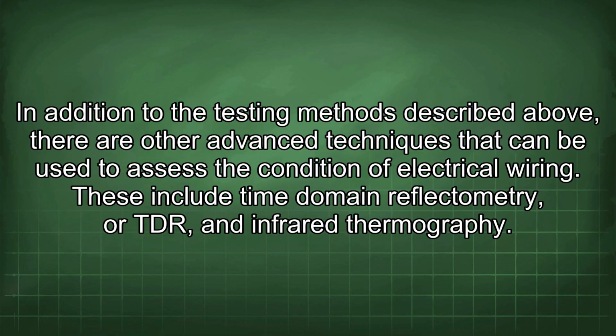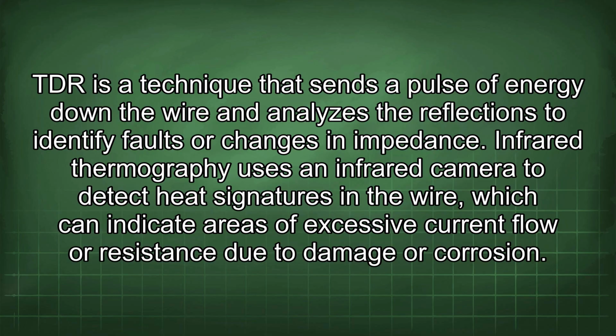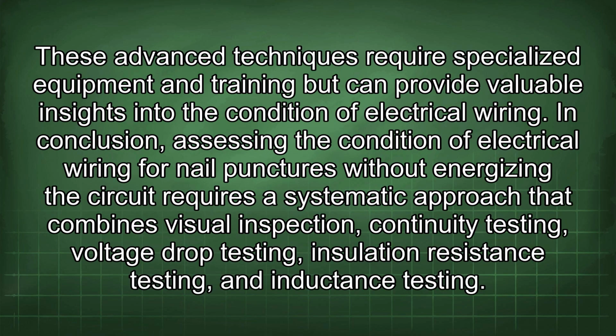In addition to the testing methods described above, there are other advanced techniques that can be used to assess the condition of electrical wiring. These include time domain reflectometry, or TDR, and infrared thermography. TDR is a technique that sends a pulse of energy down the wire and analyzes the reflections to identify faults or changes in impedance. Infrared thermography uses an infrared camera to detect heat signatures in the wire, which can indicate areas of excessive current flow or resistance due to damage or corrosion. These advanced techniques require specialized equipment and training but can provide valuable insights into the condition of electrical wiring.